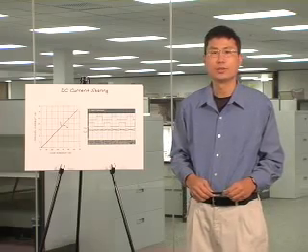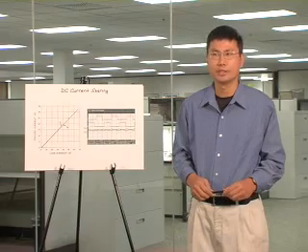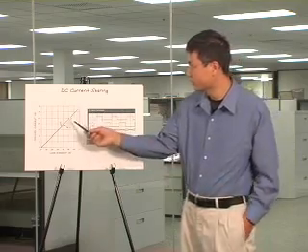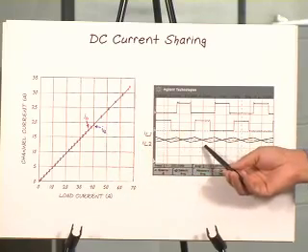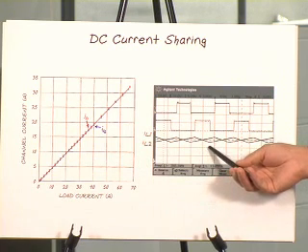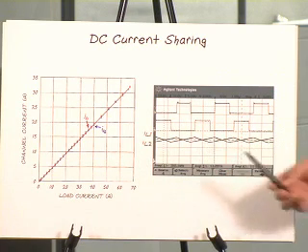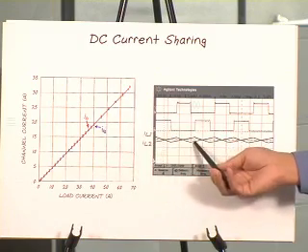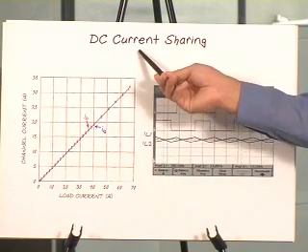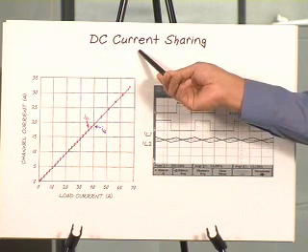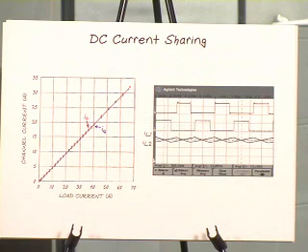Regardless of voltage mode or current mode control, if you open a vendor data sheet, you usually see very good current sharing curves or waveforms that show profile matching between channels. However, what I want to remind you today is, this nice current sharing curve or waveforms are only for conditions which we call DC current sharing or static current sharing. What the vendors don't show you is the dynamic current sharing under transient conditions, such as power-up, power-down, load-step, or short-circuit conditions. The current sharing under those conditions is important, and that's something I want to show you today.